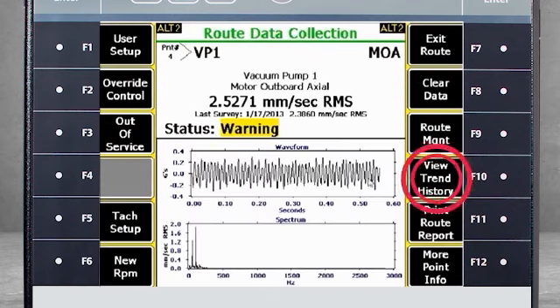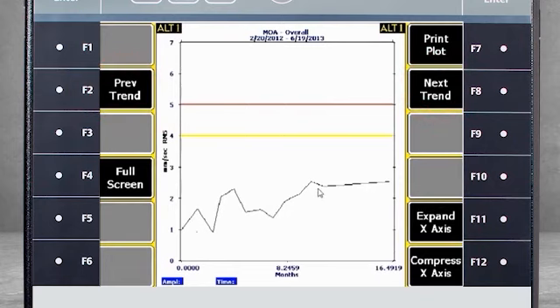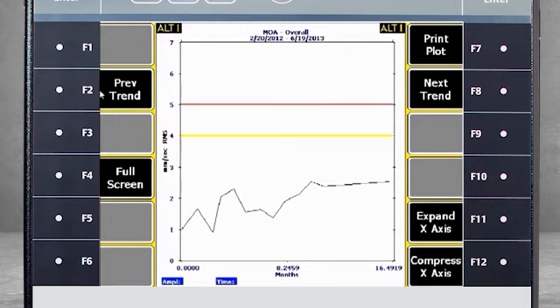When you select F10 View Trend History, you will see a trend plot that can include up to the last 24 measurements taken. F2 and F8 allow you to toggle between the narrow bands. This is a very powerful analysis tool — if on a certain point you noted a very high value, it may be useful in the field to know if this value is new or if the value has been high for a while. Knowing this could impact what you do next.